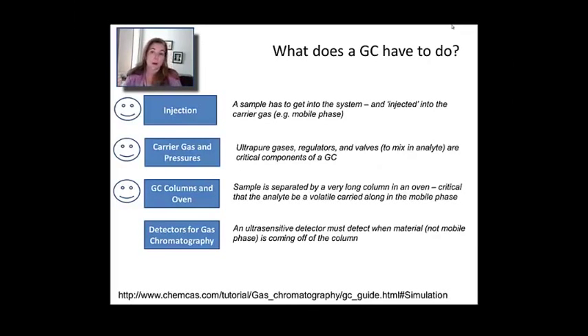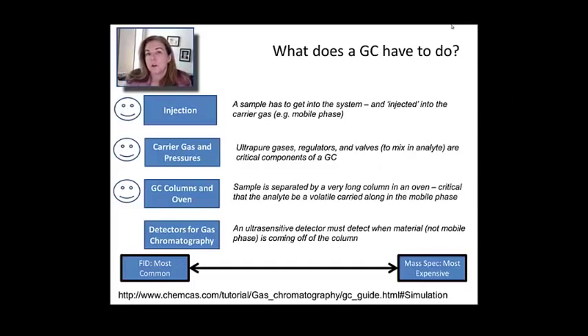They have to be able to see relatively small nanogram amounts of material, and they need to respond quickly on the order of a second. Those are pretty tall orders for a lot of detectors. The development of detector technology has really gone hand in hand with the development of those really narrow, small columns. One would be the flame ionization detector, and then the other is the mass spec. Those are, in my experience, the most common ones you'll find in research laboratories.